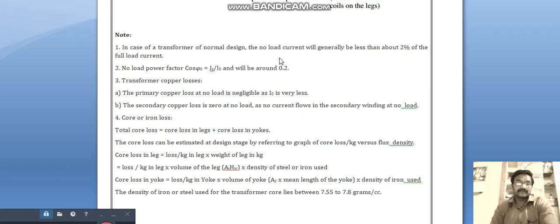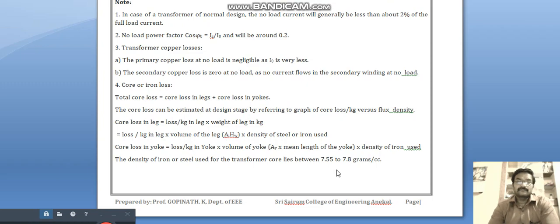Core loss in yoke: loss per kg in yoke multiplied with volume of yoke, Ay multiplied with mean length of the yoke and density of iron used. The density of iron or steel used typically lies between 7.5 to 7.8 grams per cc. Thank you.